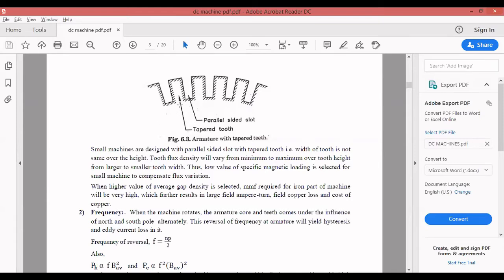To keep hysteresis and eddy current losses within the limit, a DC machine with high frequency of reversal — meaning more poles — should not be designed for a large value of specific magnetic loading. If you want to select a large specific magnetic loading, ensure the number of poles is minimum. Due to frequency of reversal, there will be eddy current loss. The number of poles is selected depending on the rating of the machine.